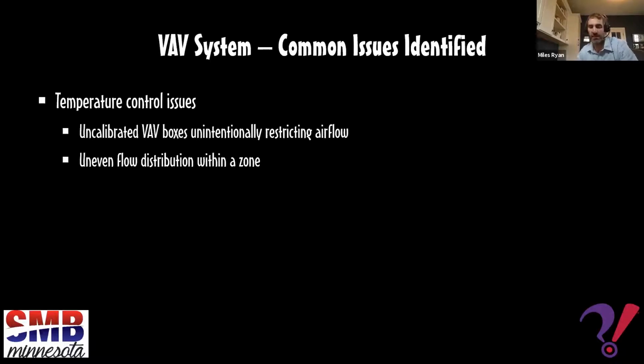But while I was there, some of the facility operators mentioned that there are some spaces that have really poor temperature control, and some of those spaces have bad air movement, and they didn't know why. In a quick review of the BAS, we found an uncalibrated, or actually in a couple of cases, a failed airflow sensor in those VAV boxes. The VAV box was basically thinking that it had like 1,000 CFM of air, which was well over set point. It started restricting down. Eventually that VAV box damper was at 0% open. There was no airflow, but it was thinking there was airflow. So therefore no airflow was provided to the space, and no temperature control could be done in the space.